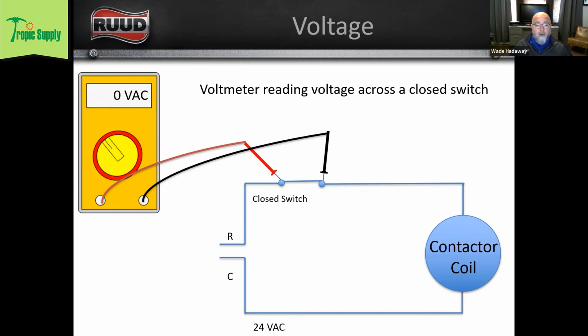Now, if we're reading across a switch and we read voltage, if I was reading 5 volts across this switch, when I go down and measure across my contactor coil, you'll see that my voltage there would only be 19 because we're losing 5 volts here. We're not now, right? We have a really good set of contacts. We have a closed switch. We're reading 0 across our switch.